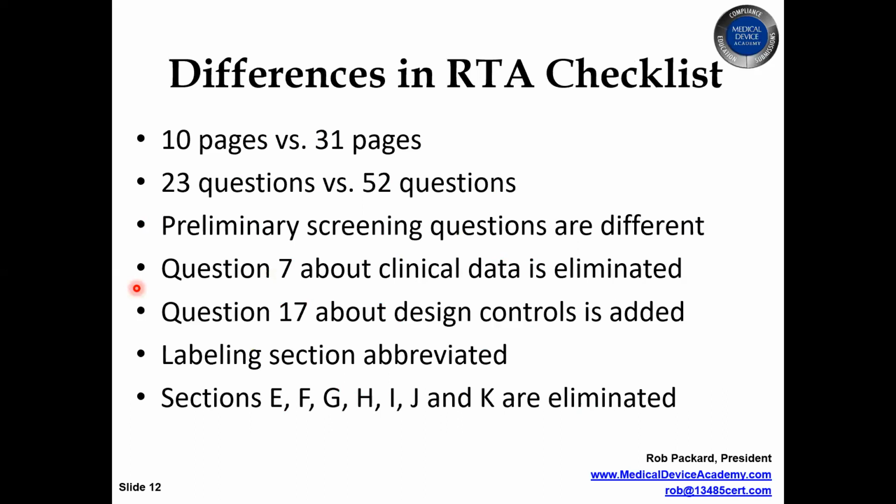Question 17 about design controls is an addition. So if you've ever seen a statement declaring conformity to design controls, that's intended for a special 510K. You're not required to submit that for a traditional 510K. So you should have a form letter set up just for that. I actually don't have a form for that because I've never had anybody ask me to do a special 510K.